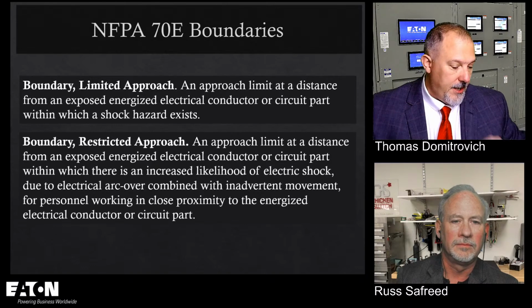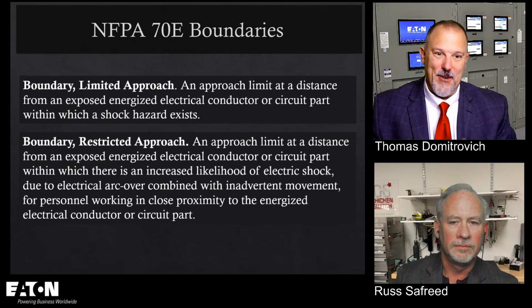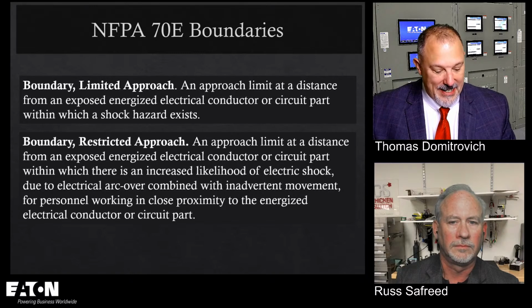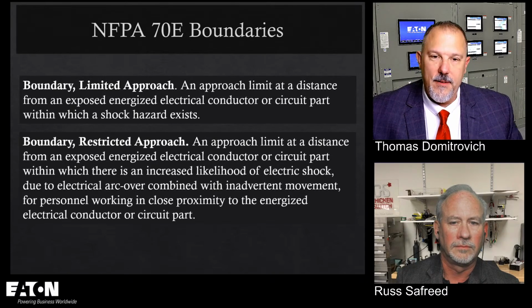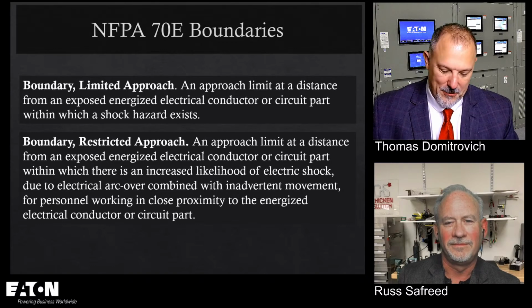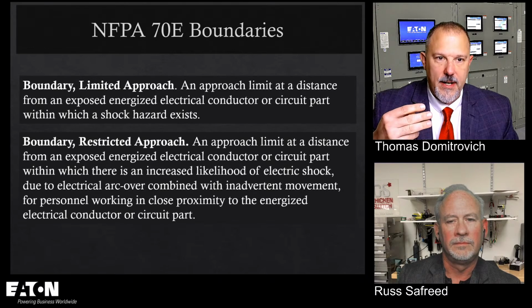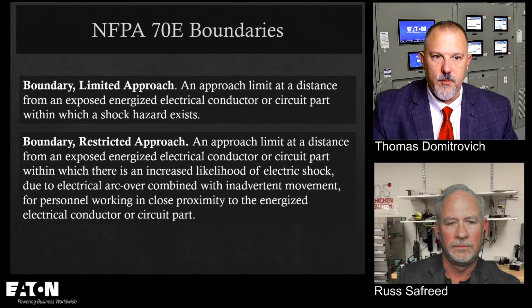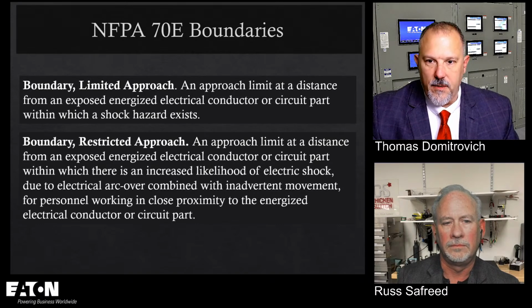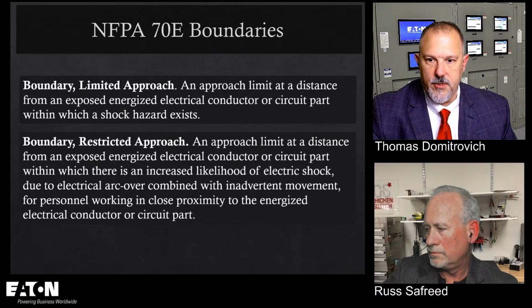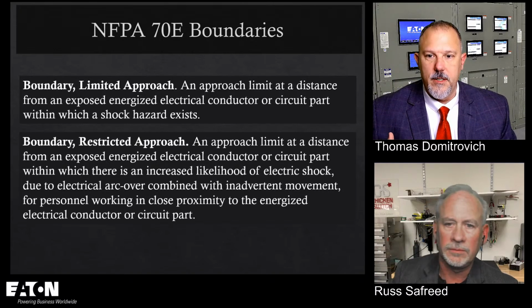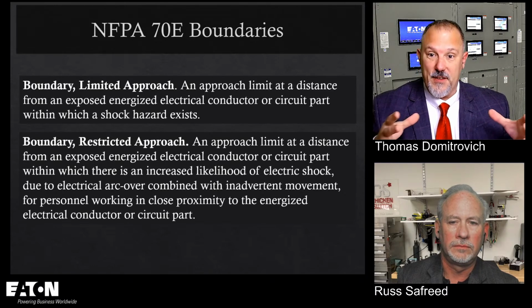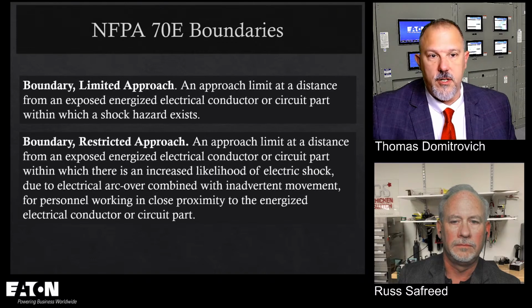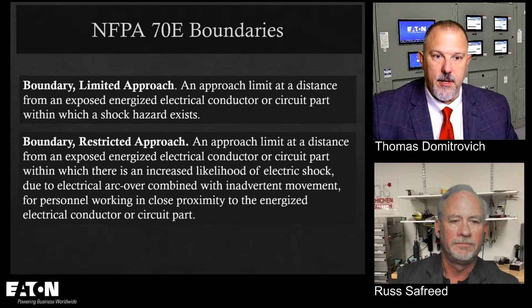So 70E gives us some definitions in Article 100, and I've got the 2021 version. These NFPA panels love to change stuff between editions, sometimes subtle but significant. They define the limited approach and restricted approach boundaries. There's a difference between an arc flash boundary and a shock boundary. In some cases the arc flash boundary may be smaller than the restricted approach boundary, or vice versa. It all depends on the calculation.